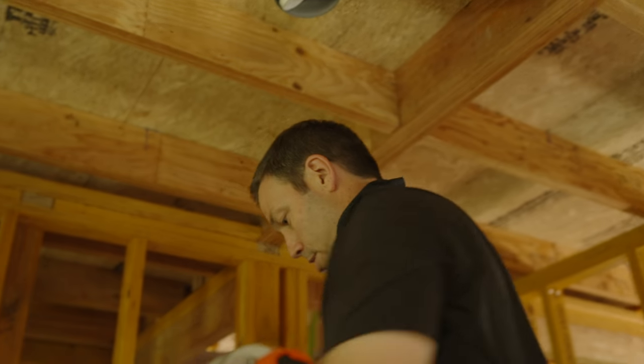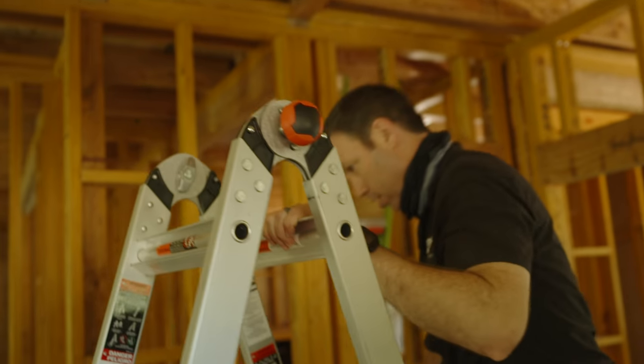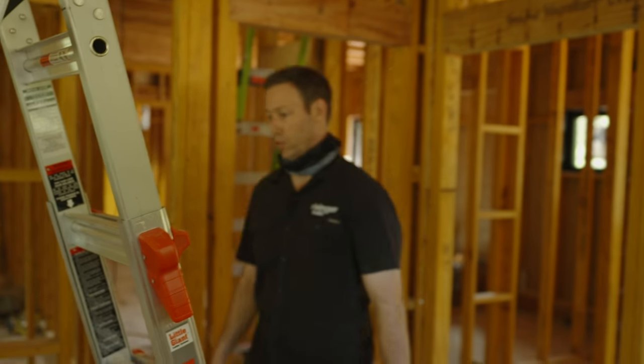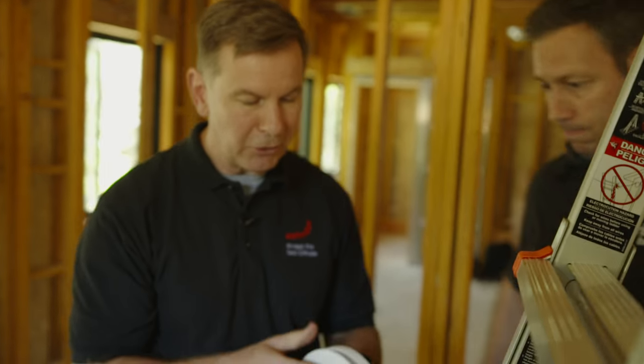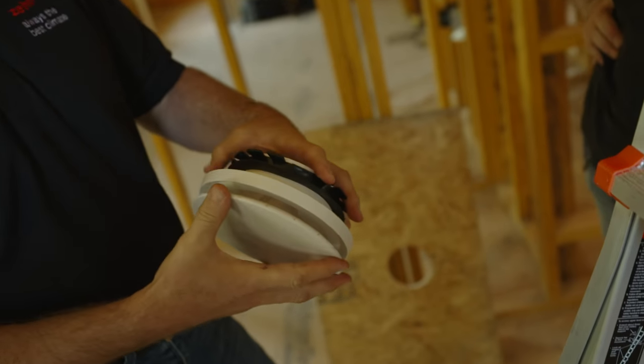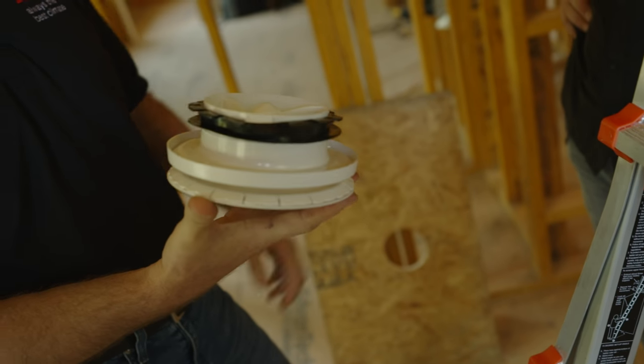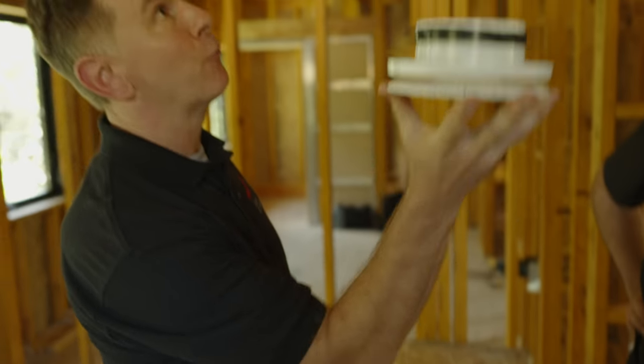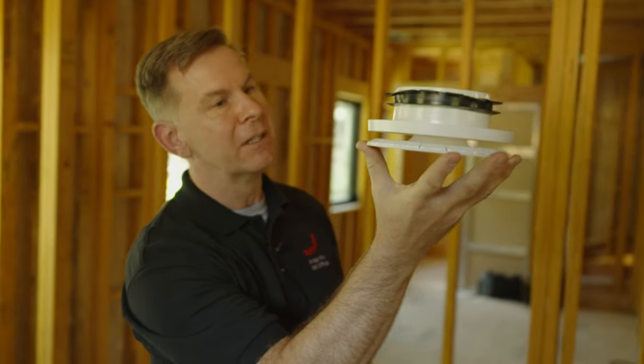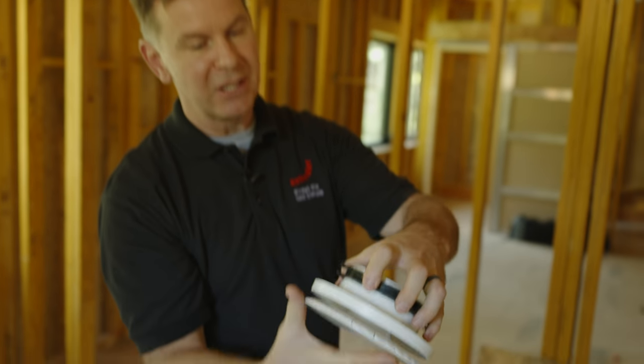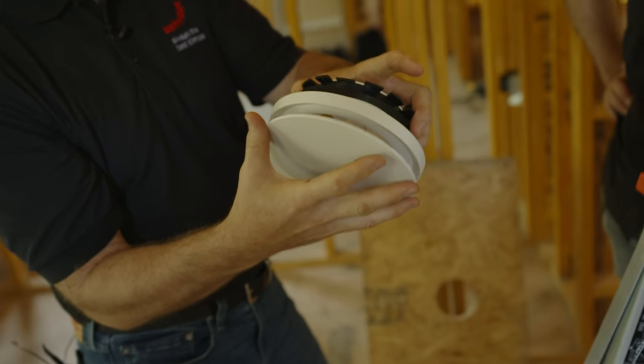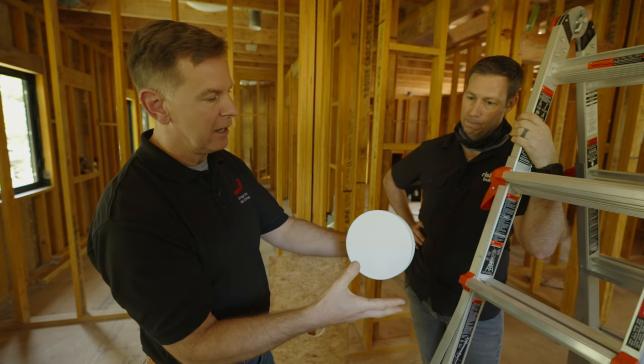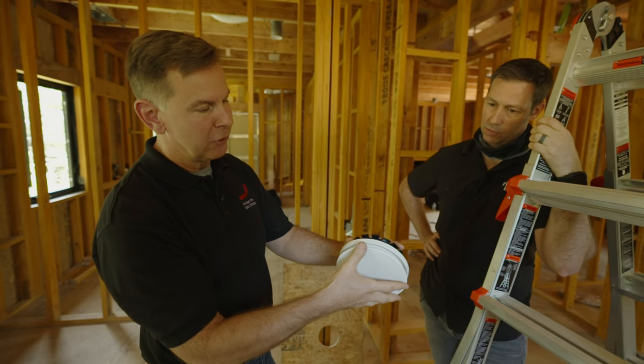And then at commissioning, talk to me about the vents that are going to be in each one of those places, Chris. Yeah, this is our Luna diffuser - this is our supply diffuser, and we also have a Luna extract diffuser. This is going to fit right up inside that 5-inch duct, and we'll air seal it with the gasket on the backside. Pre-gasketed - just pop it in and you're air sealed. Easy as that, and this can be adjusted during commissioning.